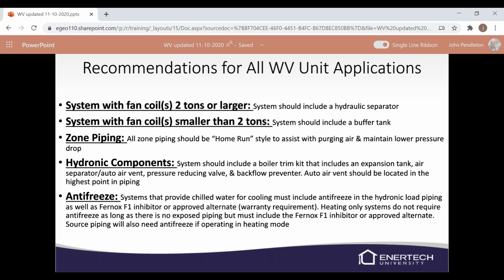Antifreeze. Make sure we're always installing antifreeze on the source, and if you're doing chilled water, that we're doing it on the load as well. Test your water. Make sure we've got inhibitors in there. Again, we have the Alpha 11 that's already got it in there, but if you're using methanol or ethanol, you're going to have to put that inhibitor in there. We recommend using Fernox. There are some approved alternatives you can use as well, but we sell and have worked with the Fernox, and it's proven to do wonders for us.